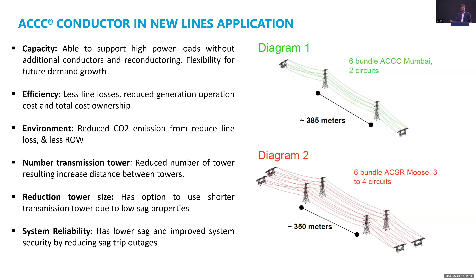This is a project from Nepal. It's a 220 kV DC line. Initially, this project was designed as a 400 kV ACSR line, right? But NEA realized they needed more power. So after doing some analysis, they decided to go with ACCC Drake. They automatically got 2 times the capacity they required. But the other thing which they got was that from a 400 kV line, they were able to bring it down to a 220 kV line. And by doing so, their right of way reduced from 52 meters to 35 meters. And if you can see in this picture, this is a mountainous terrain, right? Reduction in right of way helped them a lot, and the project schedule was reduced tremendously.